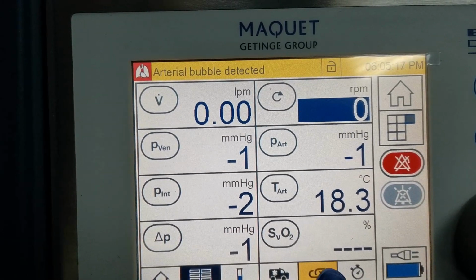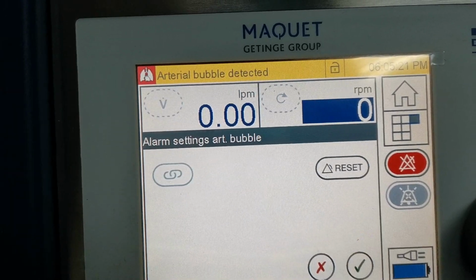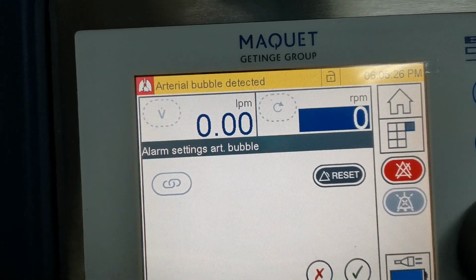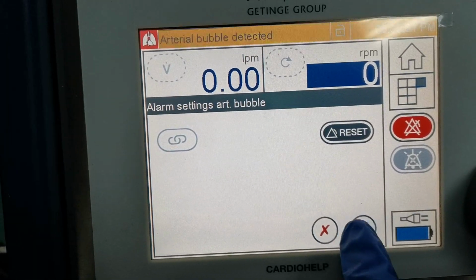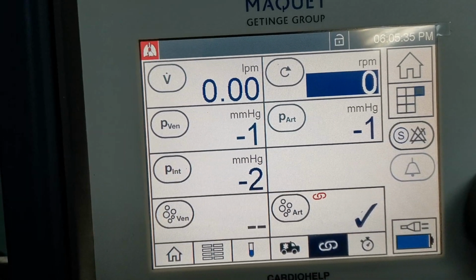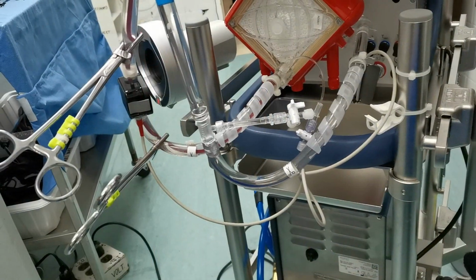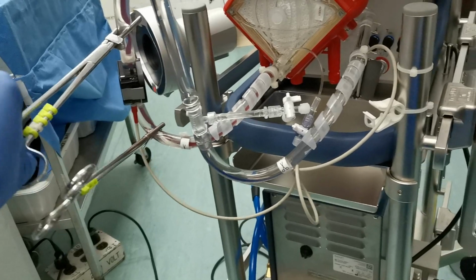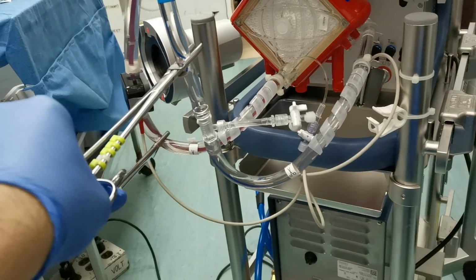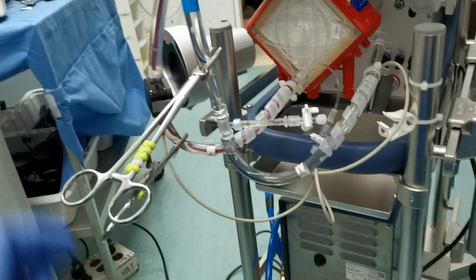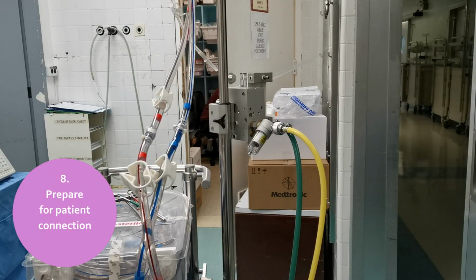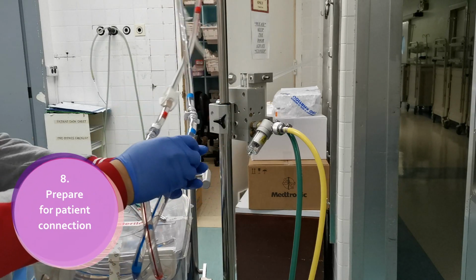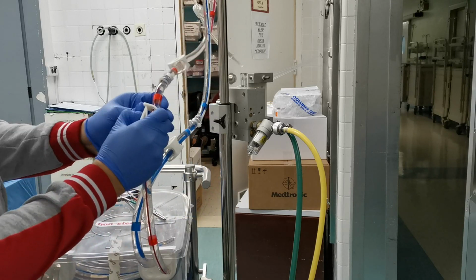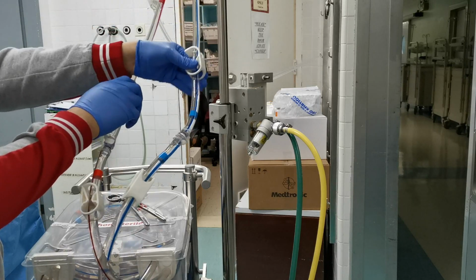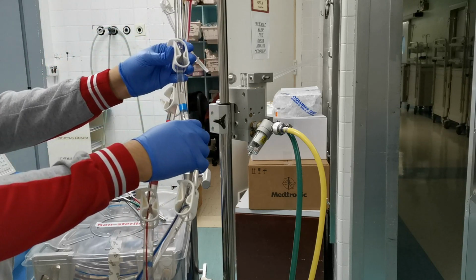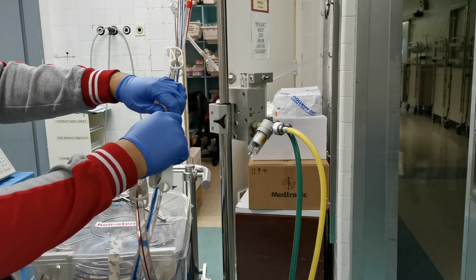Press the chain symbol on the menu bar and reset the bubble alarm setting. Lastly, deactivate the global override. Transfer one of the two clamps from the arterial line to the venous side. Clamp the distal end tubings of the tray and the priming bag. Now carefully disconnect the primed circuit from the priming bag.